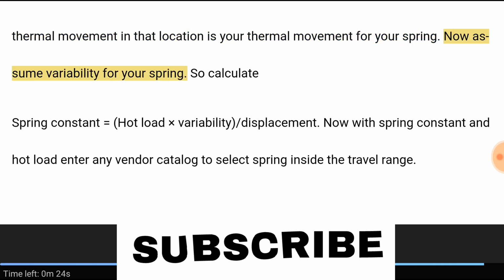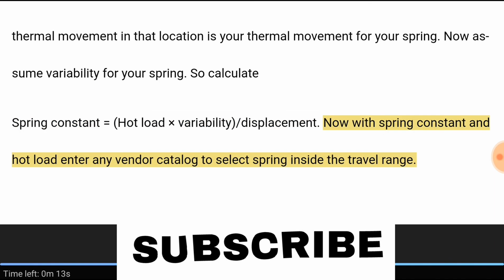Now assume variability for your spring. So calculate: spring constant equals hot load times variability divided by displacement. Now with spring constant and hot load, enter any vendor catalog to select a spring inside the travel range.